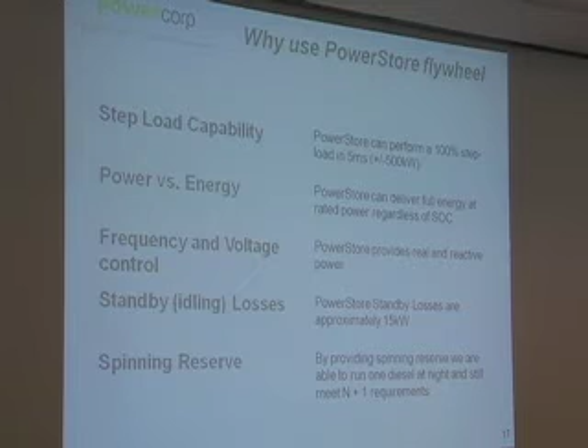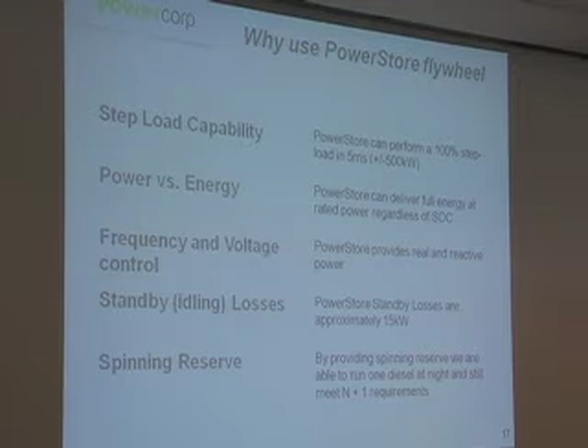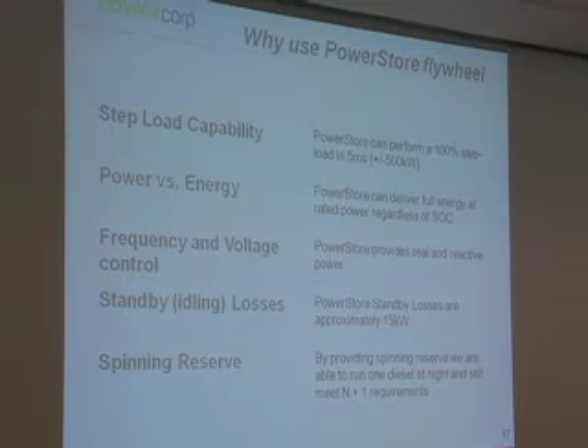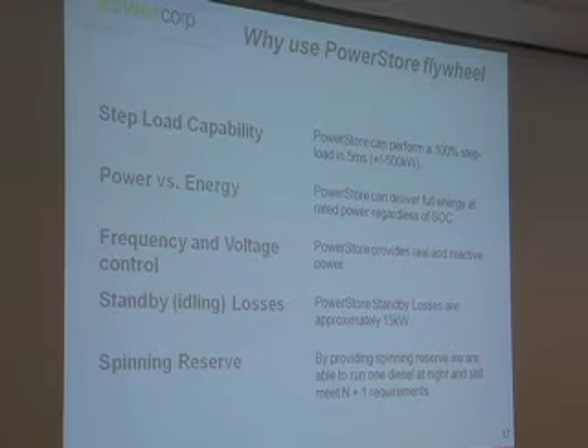A simple analogy would be having to put another diesel online, and they can run down to about 10% of their nominal rated load, so you're talking about an extra 32 kilowatts worth of diesel just on site. That's a very simplistic way of looking at it, but it gives you a bit of an idea. And also, the spinning reserve allows us to run one diesel at night time. So when the solar's not there, rather than having to run two diesels in case one trips offline, we're able to run one, and we have had an instance where a diesel went black at night, and the flywheel held the station up for 30 seconds to bring another diesel online, and the power supply into town was uninterrupted.